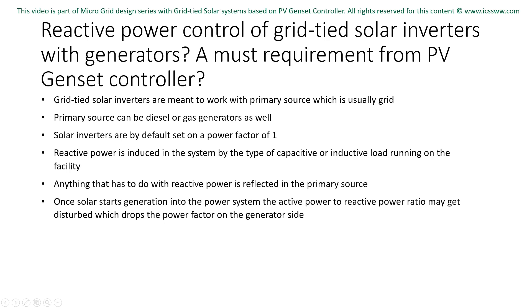Solar inverters are set to unity power factor by default. With a power factor of 1, the inverter does not generate or consume reactive power. Reactive power in a power system is the result of the nature of on-site capacitive or inductive loads. Consequently, everything related to reactive power is reflected on the generator. When solar energy begins generation in a power system, the ratio of active to reactive power can be disturbed, bringing down the power factor on the generator side.